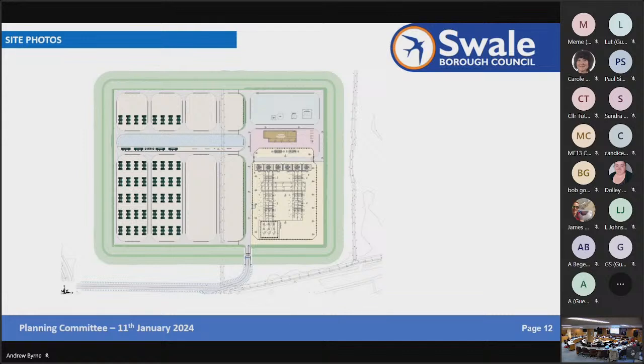So you wouldn't just turn a hose on, as was witnessed at Liverpool. Doing that will water damage modules that aren't actually in thermal runaway and will actually prolong the event, using a lot of water that won't achieve the desired effect. If you let it burn and just cool the adjacent equipment, the timeframes would have been a lot quicker.